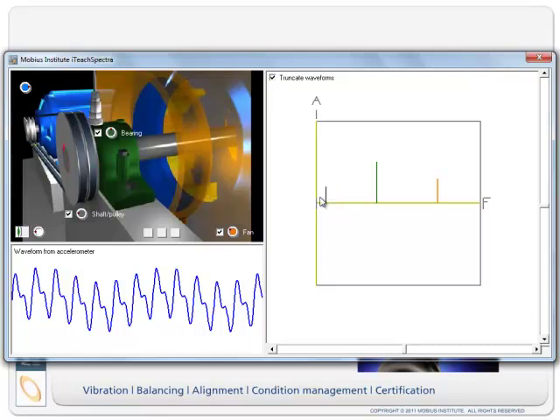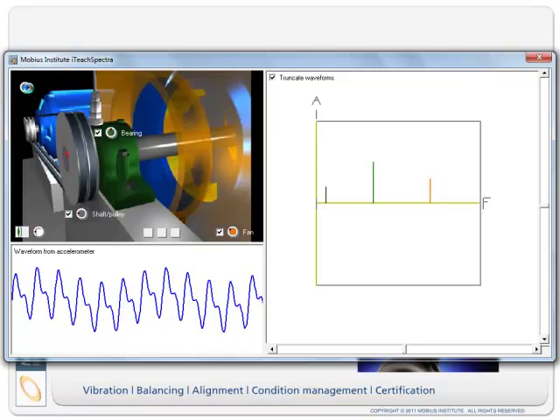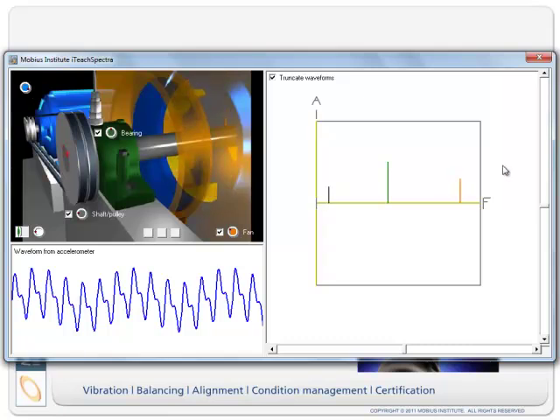And because I know I've got say 10 blades, then the distance between here and there is a tenth of the distance between here and there because there were 10 blades. And that will always be the case. Even if we speed up the motor a little bit, the green peak will move by 10% and the orange peak will move by 10%. But it's a greater movement. So it's a great simulator for explaining what's going on because now you can look at the spectrum and visualize those time waveforms behind each one of those peaks.